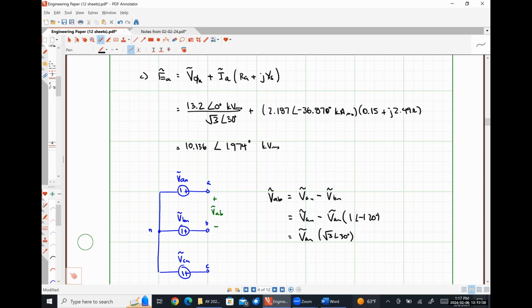So that phase change that happens when we go from line to line to line to neutral winds up giving us a voltage that is about 1 kV less in magnitude than if we had neglected it, right? That's a pretty appreciable error in our calculation.